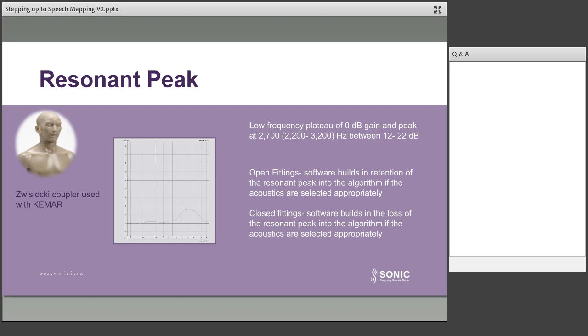And so when you put open in your fitting software, the fitting software takes into account that you're going to retain that resonant peak. Now, if you have a closed fitting and you put that into the software, then your fitting software goes, closed fitting, that's going to actually reduce or remove the resonant peak. So I'm going to have to build that in on top of everything else that I do. And so setting the right acoustics in your fitting software is critical as well.